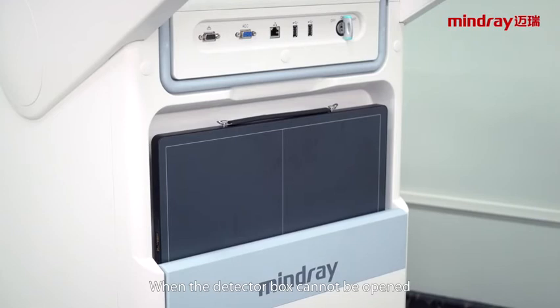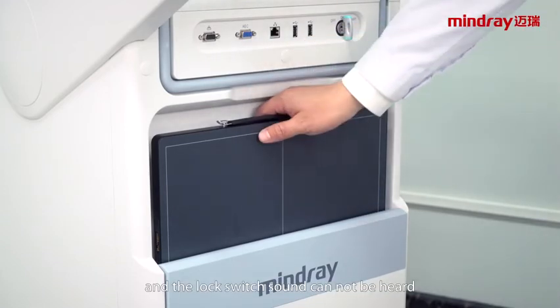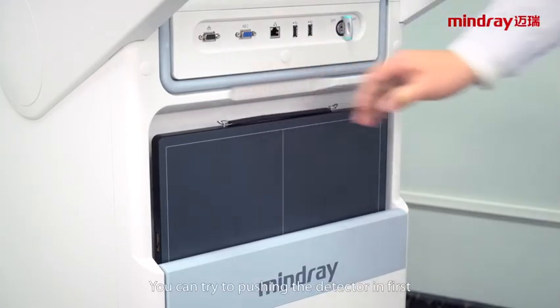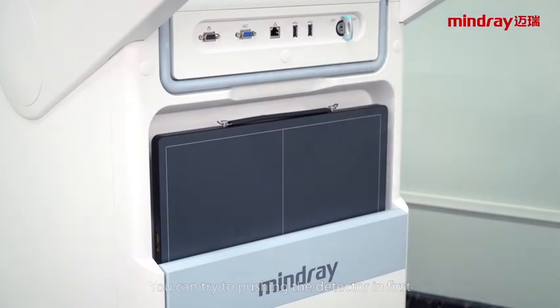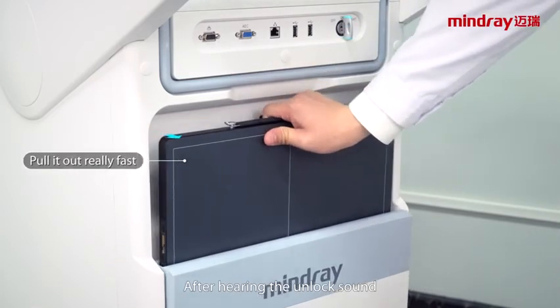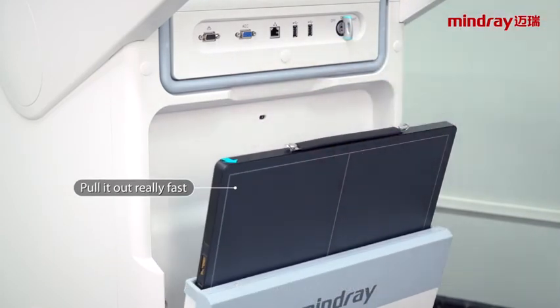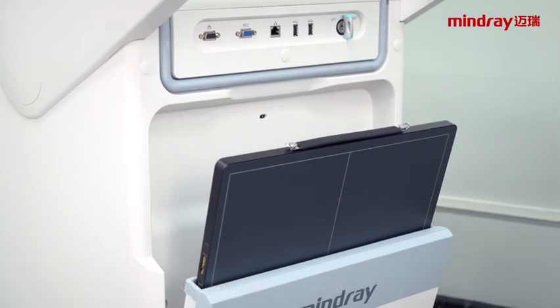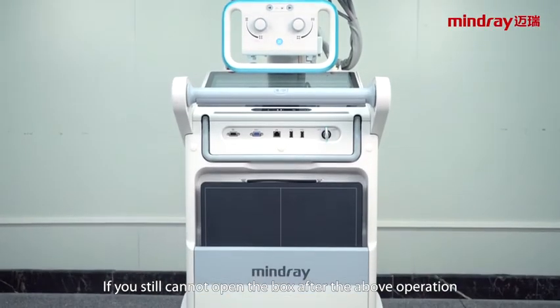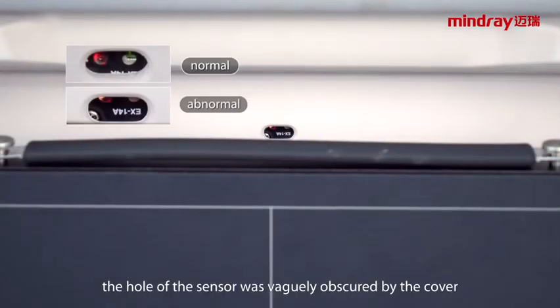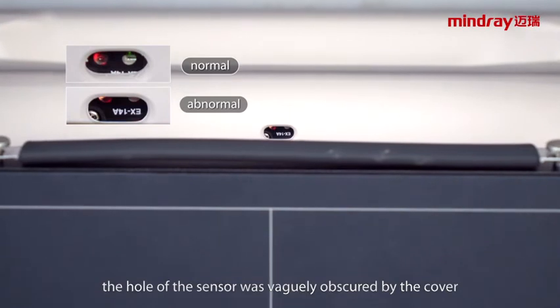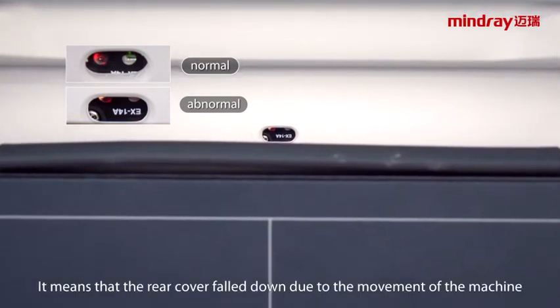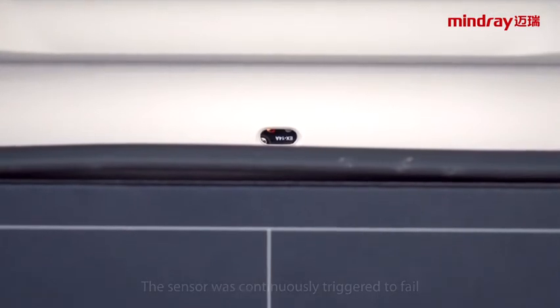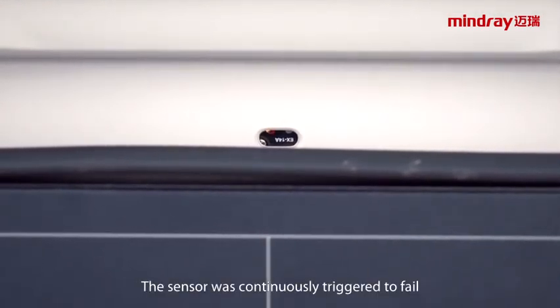When the detector box cannot be opened and the lock switch sound cannot be heard, you can try pushing the detector in first when you trigger the sensor of the detector box. After hearing the unlocked sound, pull it out quickly and then open the detector box. If you still cannot open the box after the above operation, and at the same time the hole of the sensor is vaguely obscured by the cover, it means that the rear cover fell down due to the movement of the machine. The sensor was continuously triggered and failed.